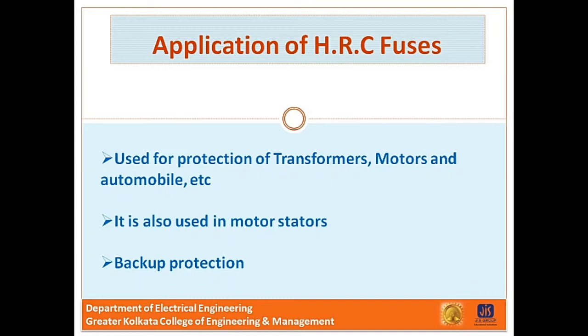Now both the fuse and circuit breaker complement each other in a low voltage system, and the fuse can be used to provide backup protection to the circuit breaker with high breaking capacity. HRC fuse is a low voltage fuse. Now there is another low voltage fuse, the semi-enclosed rewirable fuse. The primary objection of low and uncertain breaking capacity of the semi-enclosed rewirable fuse is overcome by the HRC cartridge fuse.